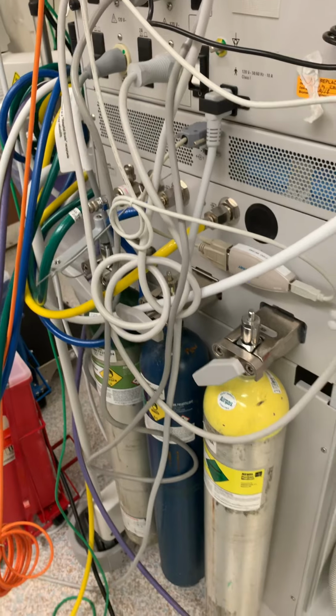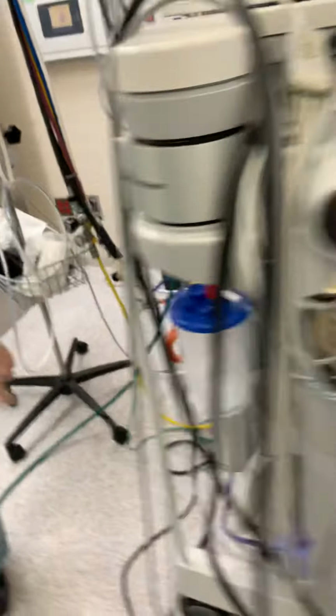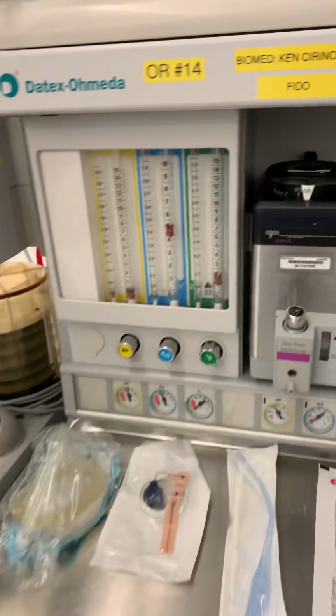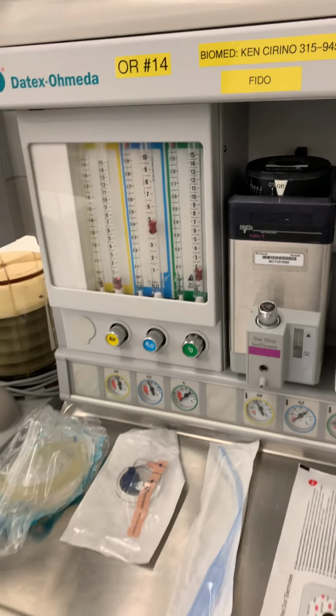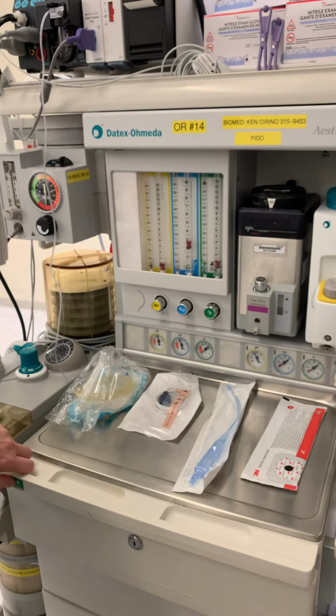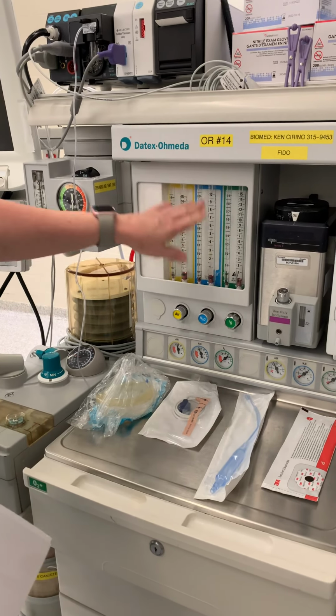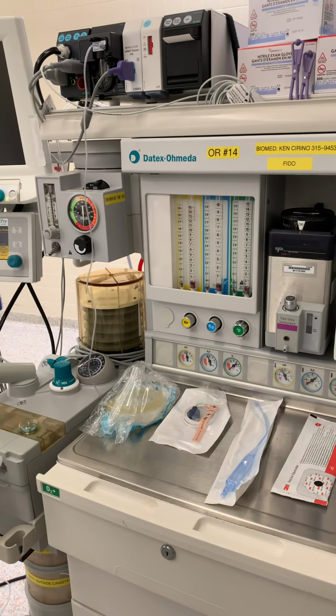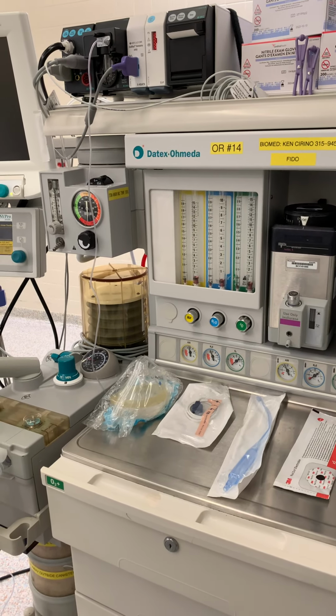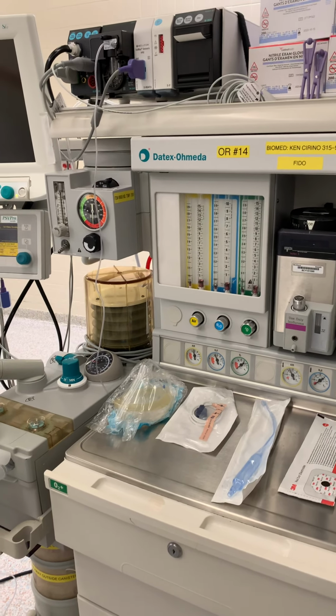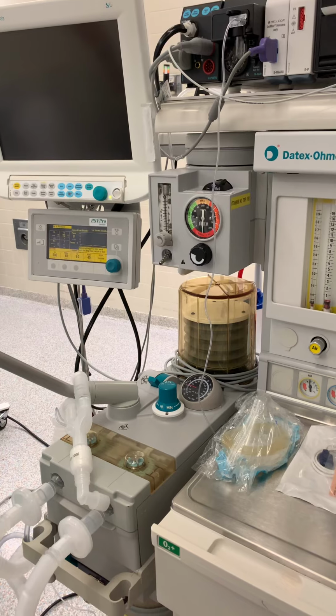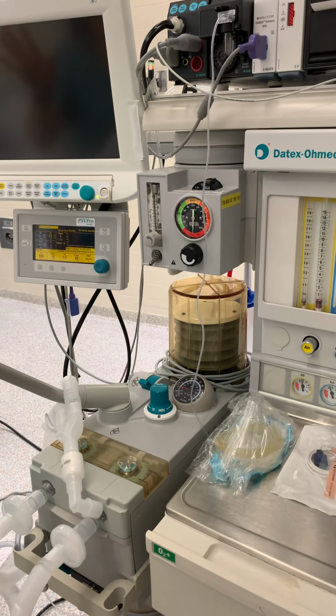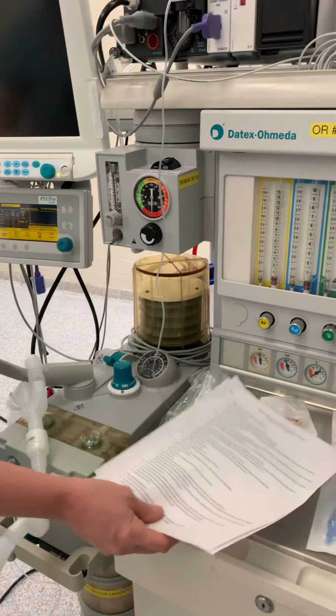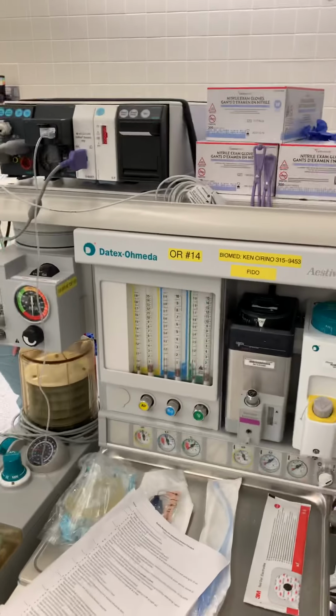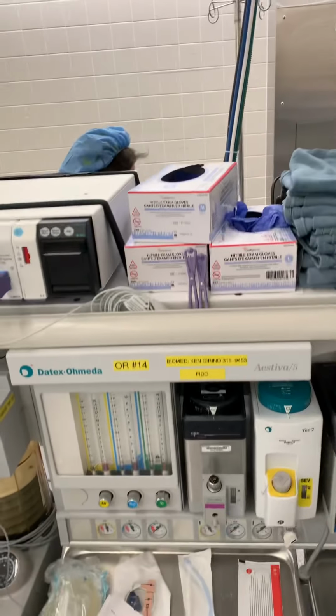So righty-tighty, I've turned off the oxygen cylinder, and now if you go back, you should notice that as the machine loses its oxygen, watch the nitrous fall. And that's exactly what should happen. So now we again should hear the audible alarm that is signifying that we again have no oxygen coming to the machine. Now you can just stay here, and I'm just going to go hook up the pipeline that we disconnected, and we'll move forward with our test.